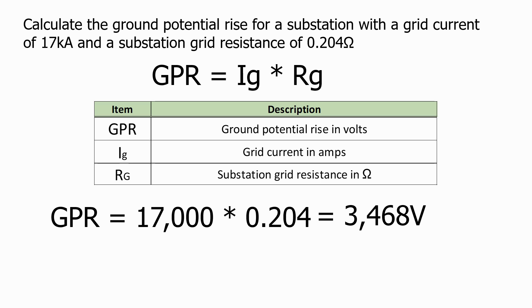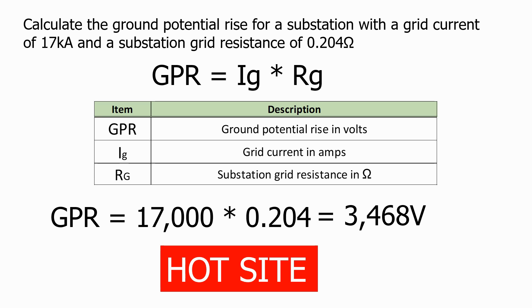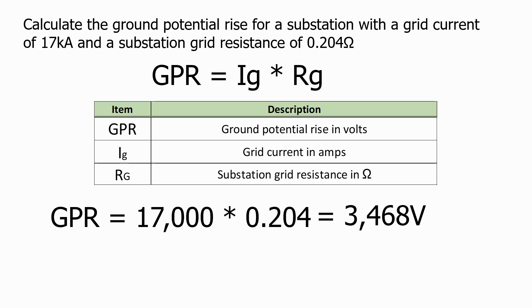This means that looking remotely at the substation, all of the ground below the substation will rise 3468 volts higher than remote Earth. Many utilities define a substation that has a ground potential rise greater than 650 volts as a hot site, and this substation would therefore fall into that category.